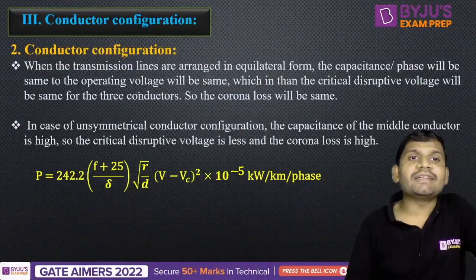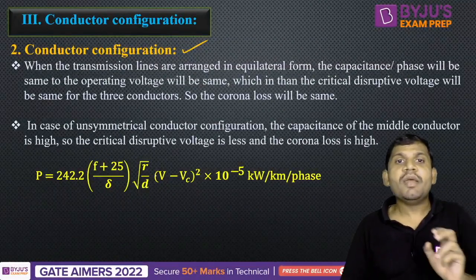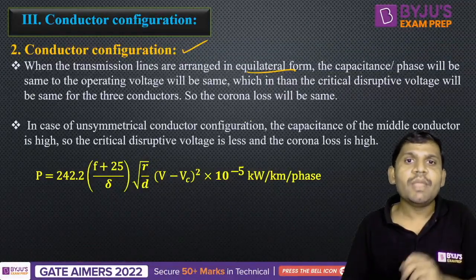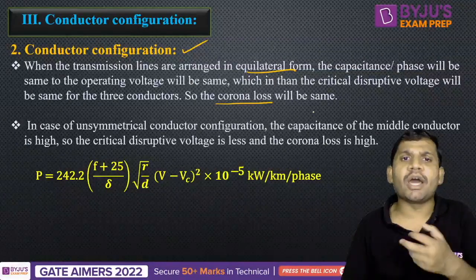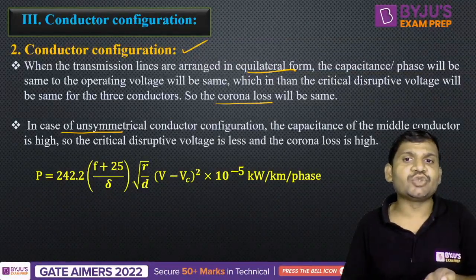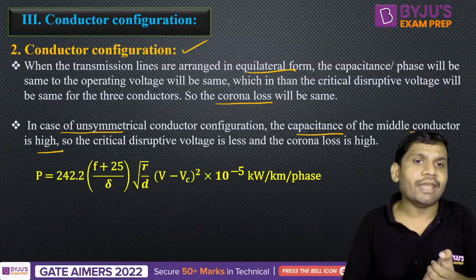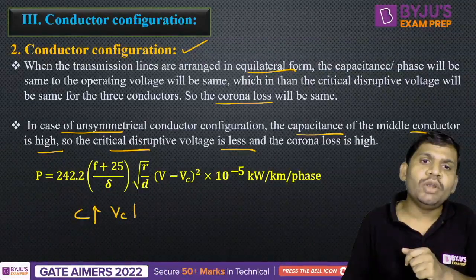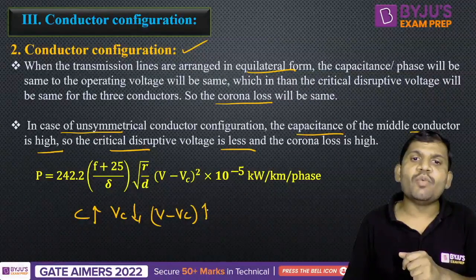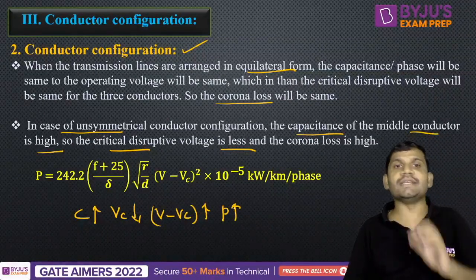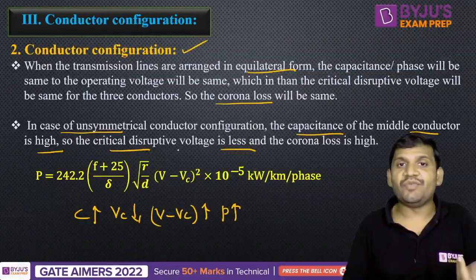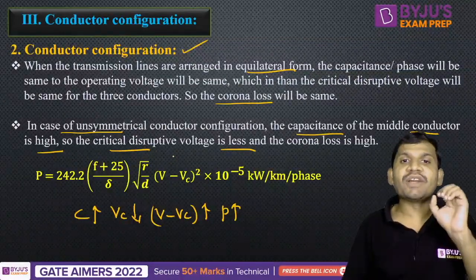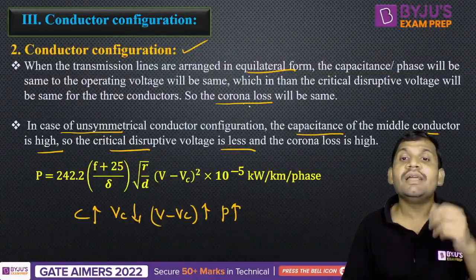One more important factor with respect to conductor configuration is the arrangement. For symmetrical (equilateral) configuration, there is no significant corona effect. But in unsymmetrical configuration, the capacitance of the middle conductor is very high, so the critical disruptive voltage is less. If the capacitance increases, Vc reduces, V minus Vc increases, and corona loss also increases. For unsymmetrical configuration, corona loss is more compared to symmetrical configuration.